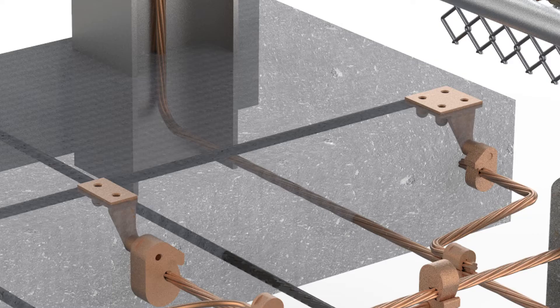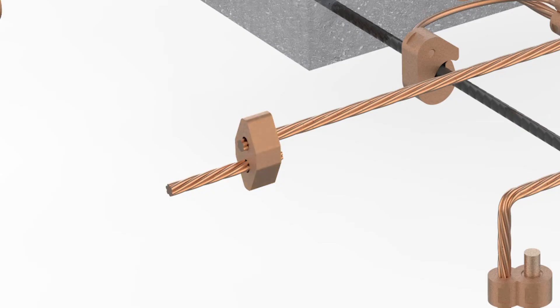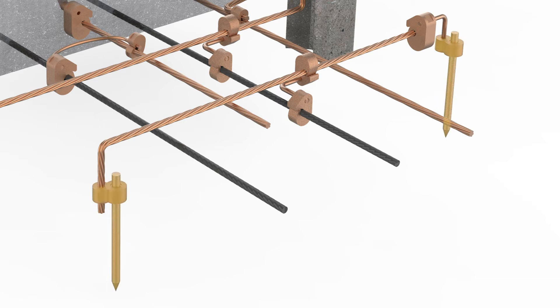Run and tap connections, cast copper plate for concrete pads, 90-degree intersecting grid connections, tap and splice applications, and lastly, the connection of the vertical ground rod to horizontal grid conductor or rebar.